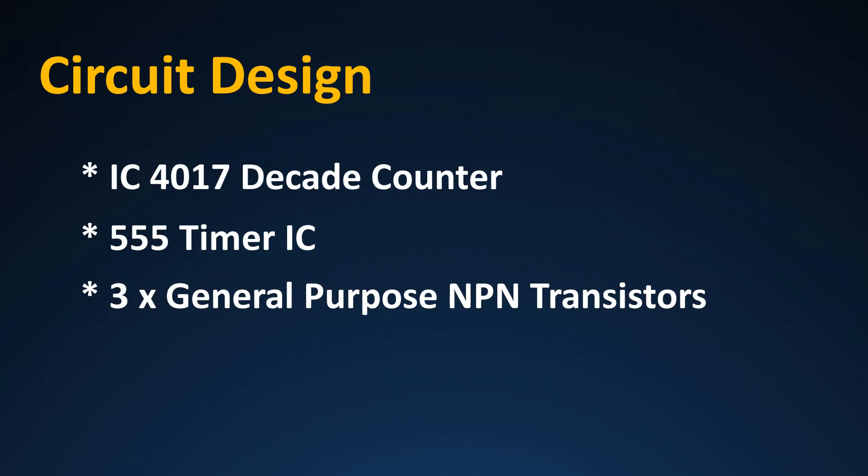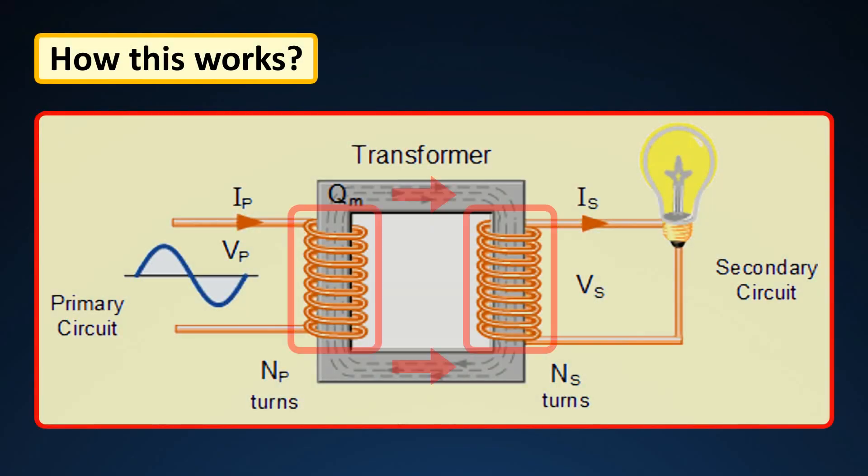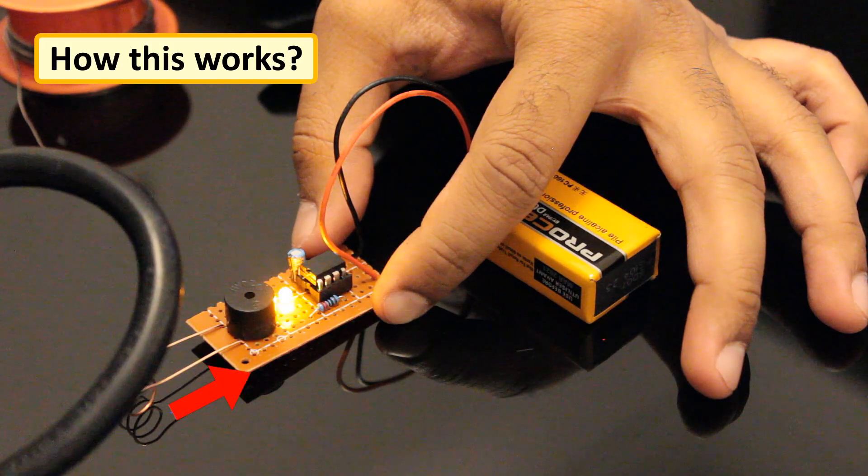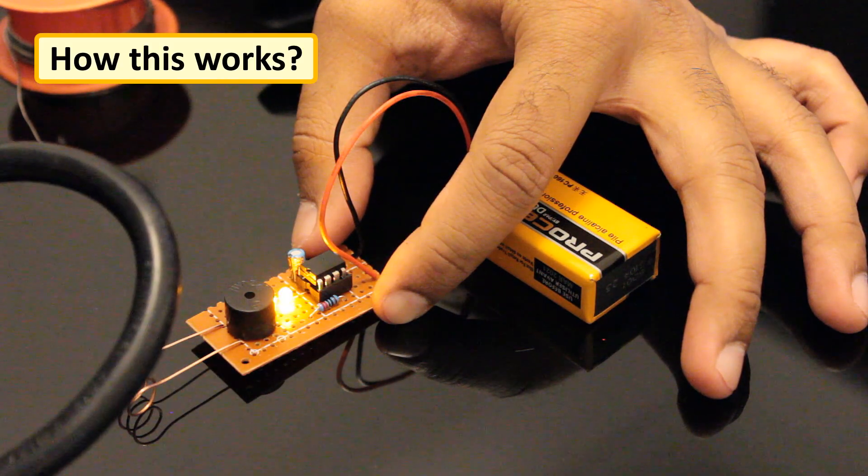All these voltage detectors work on a simple principle of electromagnetic induction. A magnetic field is produced around a current carrying conductor and if current through the conductor is alternating current, the magnetic field produced varies periodically. When we place an antenna near an AC energized object, a small current gets induced into the antenna due to electromagnetic induction.